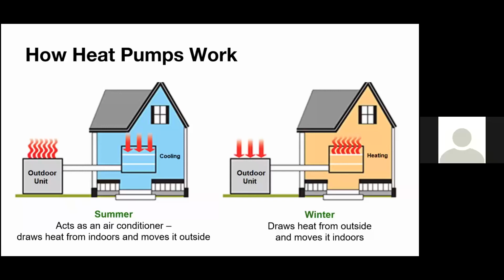So now you have a 50-degree temperature difference between that 20 degrees outside and 70 degrees in the space that compressor needs to work harder and more electricity needs to go into it. So there's a couple things that happen as it gets colder. One of them, again, is you have to fight that bigger and bigger temperature rise. There's less and less heat in the air as it gets colder. However, until you get to absolute zero, there's always going to be heat in the air. And then 0 degrees might be cold for us as humans, but for the right refrigerant and the refrigerant cycle, there really shouldn't be any issues there.